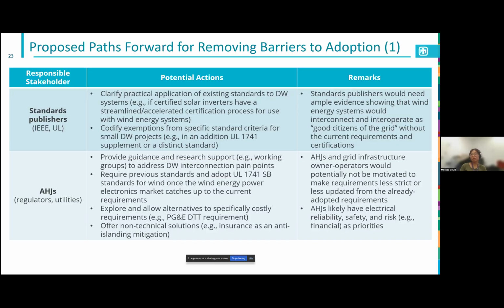AHJs may also have the agency to explore alternatives to requirements that are specifically costly in practice. For example, in California, PG&E requires DERs to undergo an anti-islanding screening test, or risk of islanding test, and systems that fail the test must install a direct transfer trip device that would automatically isolate the generation section of the DER. We've heard that this requirement's implementation has been reported as costly, and in response, CPUC has created unintentional islanding working groups to look into technical and non-technical alternatives, which could then potentially be adopted as options by AHJs accordingly.